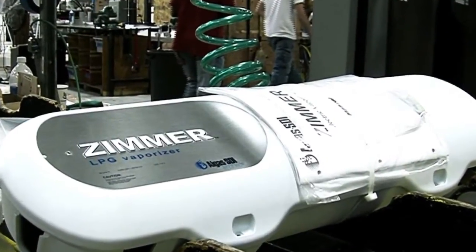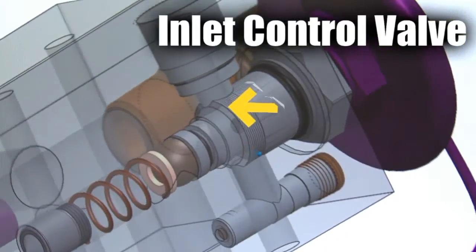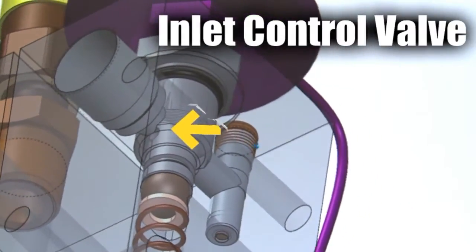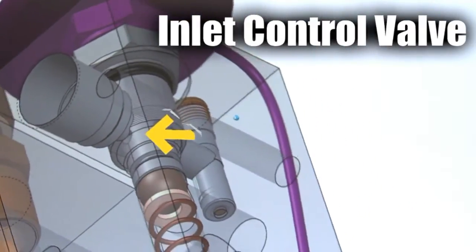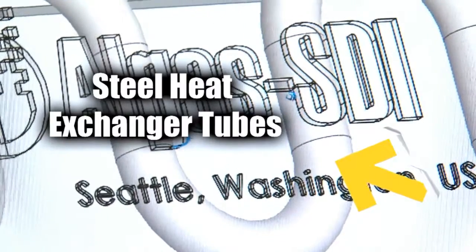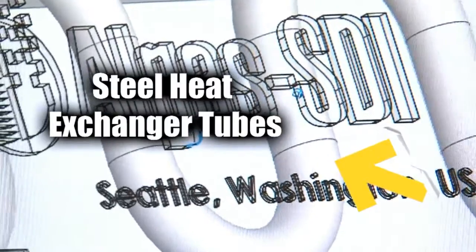Liquid LPG enters Zimmer via its inlet control valve. The inlet control valve's inverted metal-to-metal seat provides durability and prevents debris from collecting on the valve seat. Liquid LPG next enters Zimmer's steel heat exchanger tubes.